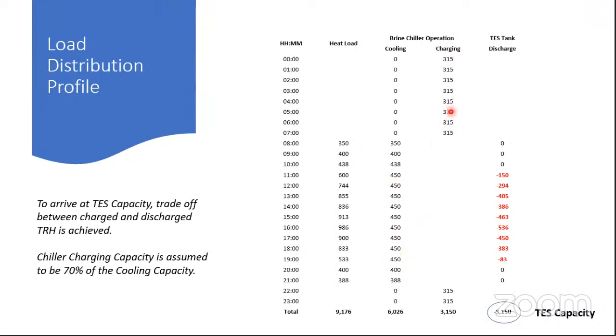So 70% is what I have assumed. 70% deration is what I have assumed. So now the trade-off is achieved between the charging capacity. This is our discharging pattern, and this is our charging. We need to make sure that this charging tonnage is equal to the discharging tonnage, because we cannot store more or charge less. We need to have enough charging hours as well, and this is the reason why we need to have that base load chiller in place to get these charging hours.